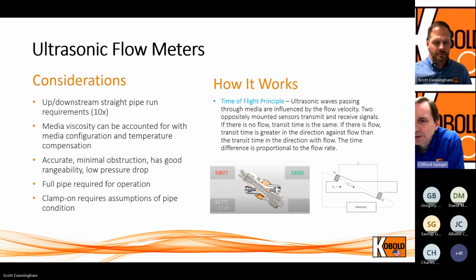Yeah, we were talking earlier: with either one of these technologies, ultrasonic or mag meters, what you're actually getting is the velocity of the liquid going through the meter. And when you get the velocity, you have a known cross-sectional area, and that's how it calculates flow rate. So really what you're doing is measuring the flow velocity. Yeah, good point. Well, that's a nice tie-in with how it works.